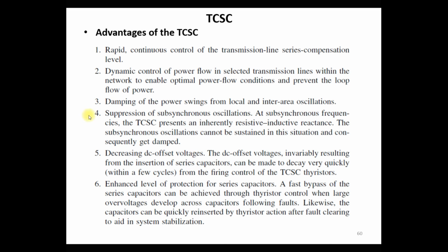Then the next advantage is the suppression of the subsynchronous oscillation. At subsynchronous frequency, the TCSC presents an inherently resistive inductive reactance. So in that case, if the TCSC is connected, we can reduce this subsynchronous oscillation, because this subsynchronous oscillation cannot be sustained in this situation when the TCSC provides the inherently resistive inductive reactance. So your subsynchronous oscillation is damped out if you connect the TCSC.